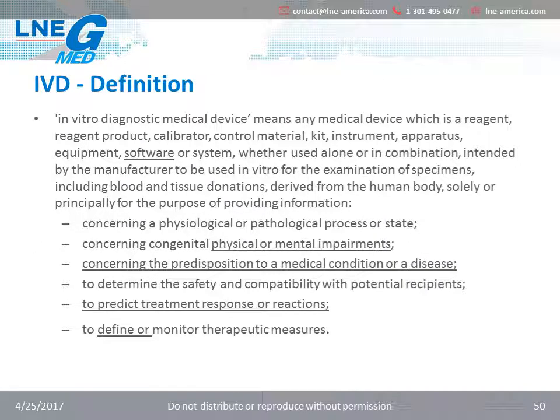There is a minor change to the definition of the IVD in the regulation, specifically the underlined portions noted here. So you'll notice that software has been specifically called out in the definition. Congenital abnormality has been clarified to specify physical or mental impairments. These are noted by the two underlined sections concerning the predisposition to a medical condition or a disease and to predict treatment response or reactions. These have both been added. And finally, clarification to define, not just monitor, therapeutic measures.